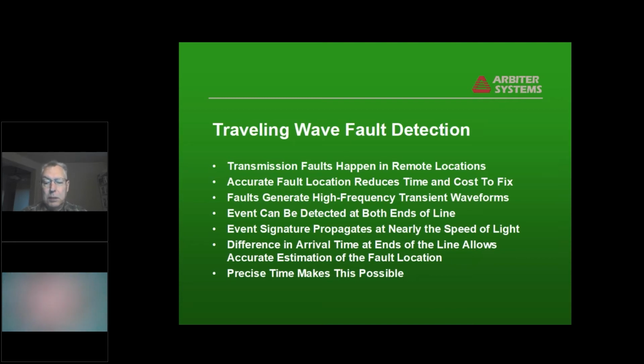It's usually nearly the speed of light because the dielectric is mainly air. So if you can measure the difference in arrival time at the ends of the line, you can calculate the fault location that matches up to that. And this is an application that requires very precise time because the speed of light is basically 1 nanosecond per foot. So if you want to know within 500 feet where the fault is, you have to be synchronized within 500 nanoseconds between the two ends of the line.